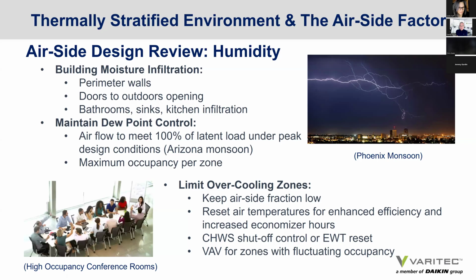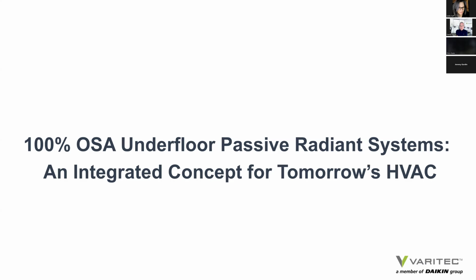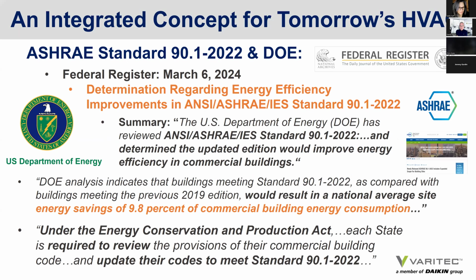So with these technologies available, we have 100% outside air systems, we have underfloor air systems, and we now have radiant technology available to us today. What if we take an integrated design approach to meet our current industry challenges? I've shown this slide before at a number of presentations, so bear with me just to revisit it. On March 6th of 2024, the Department of Energy issued the determination that ASHRAE Standard 90.1 2022 has been determined to be the energy performance baseline buildings have to meet, and municipalities have up to 2 years to incorporate its language into their codes.